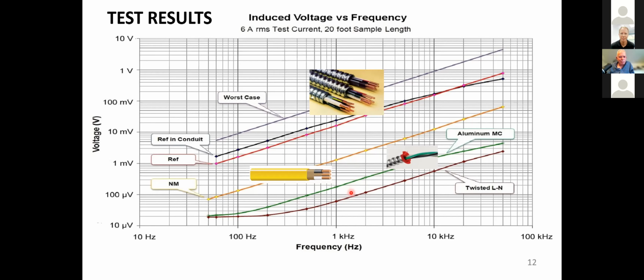It's simply not there, and it also eliminates all the inductance in the circuit by the same token. So the magic bullet with wiring is to twist the two current-carrying conductors together before you pull them into the conduit. Then it doesn't much matter where you put the ground conductor - that has the lowest induction of all. We only get up where we were getting 10 volts from a light dimmer perhaps; we're down into a millivolt or two. It's a 60 dB improvement, at least 1,000 to 1, just from that simple act.